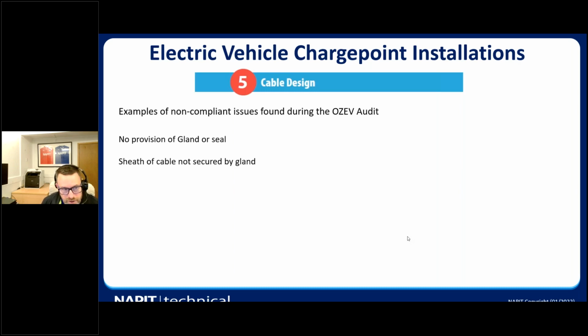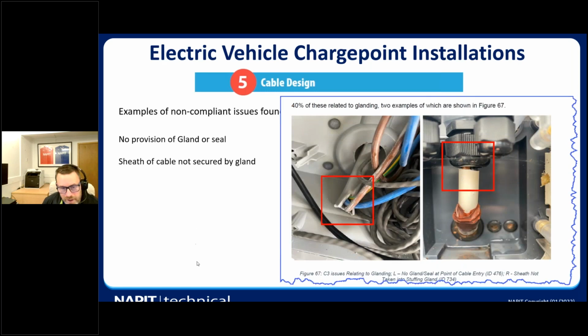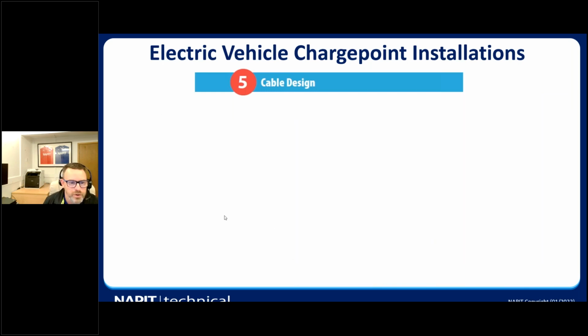So we're looking at the incorrect glands or seal. Cable sheath not secured by the glands. This is another one here. So we've got the twin earth pulled through the cable. It's not secured. There's not any termination or seal in here. The sheath of the cable is not inside the gland here. As it comes through the grommet, there's a bit of tape around it. So it's all that the cable's been secured properly, so there's no strain on the termination and no ingress of water or moisture into the EV charge point.